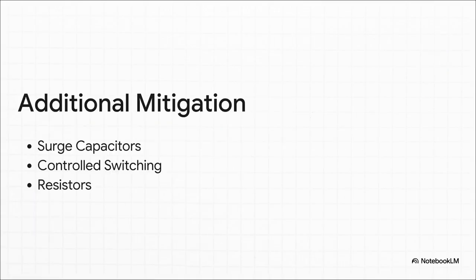But beyond surge arresters, engineers have a pretty robust toolkit for mitigation. We use surge capacitors placed directly at breaker terminals to lower the rate of rise of transient recovery voltages. We deploy controlled switching devices to perfectly time contact separation with the point-on-wave to minimize arcing. And we utilize pre-insertion resistors to add temporary series resistance to a circuit, which effectively dampens those harsh switching surges that cause slow front overvoltages in the first place.